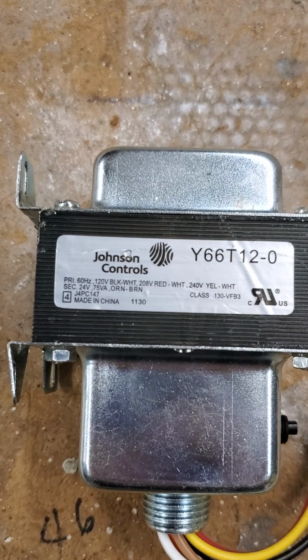So that VA part, that's how much power it can put out for a certain amount of distance. So the higher that number is, the more controllers you can actually connect to this transformer. Whereas if you had a lower number, say like 50, you wouldn't be able to put as many controllers on it. Most of the time we use 100 VA transformers, and if you're running VAV controllers, I think our standard right now is 5 controllers per transformer. And if you're running stuff like FECs or some other more power hungry controllers, you might want to step it down a couple more controllers. It all depends on the job site though.